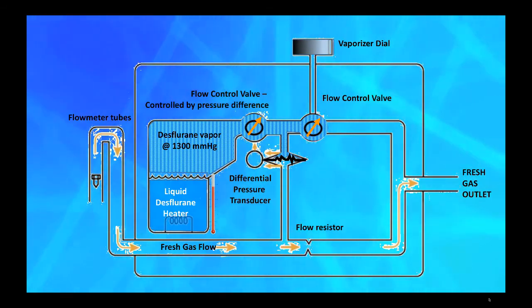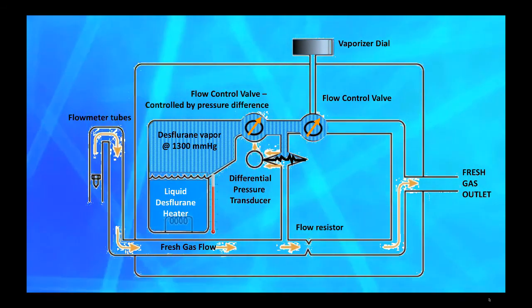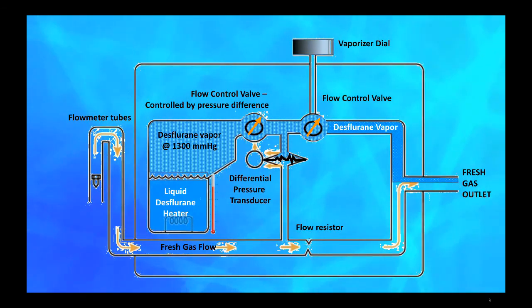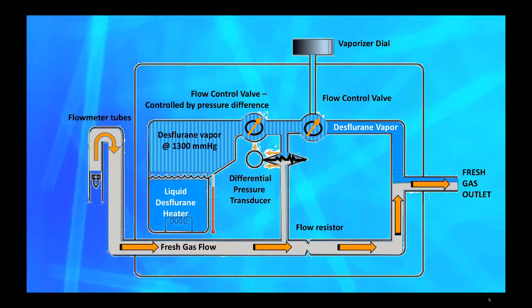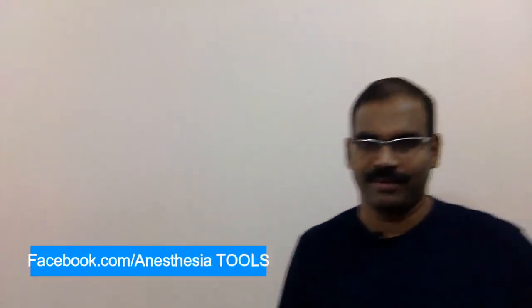The second flow control valve is controlled by us through the vaporizer dial. The reason why we need almost two atmospheric pressure is to act as a driving pressure so that the vapor joins the fresh gas flow. You can see the fresh gas flow and the gas-vapor blending.